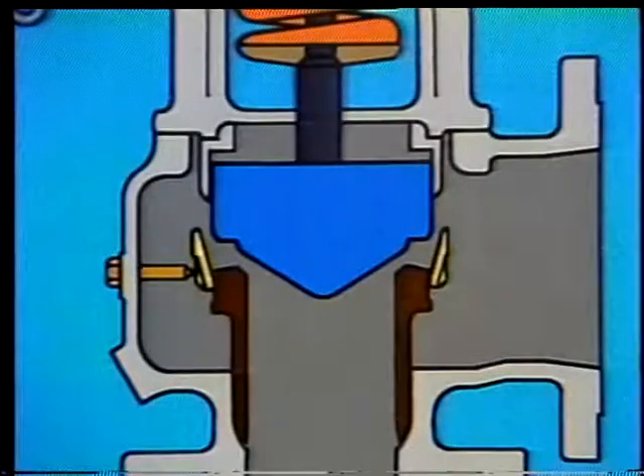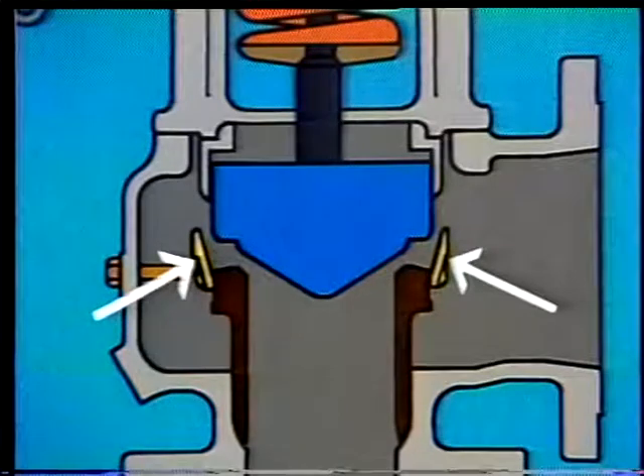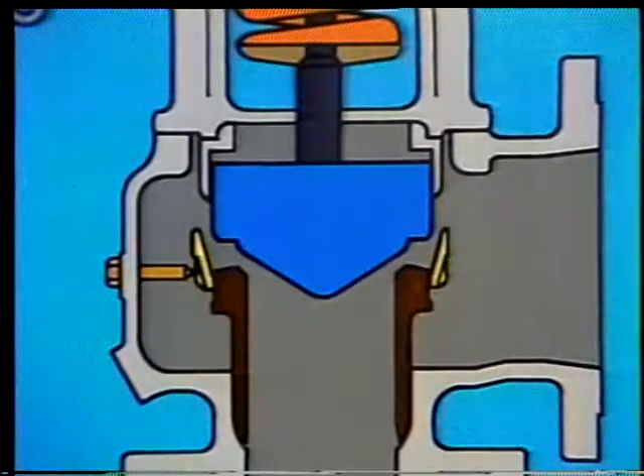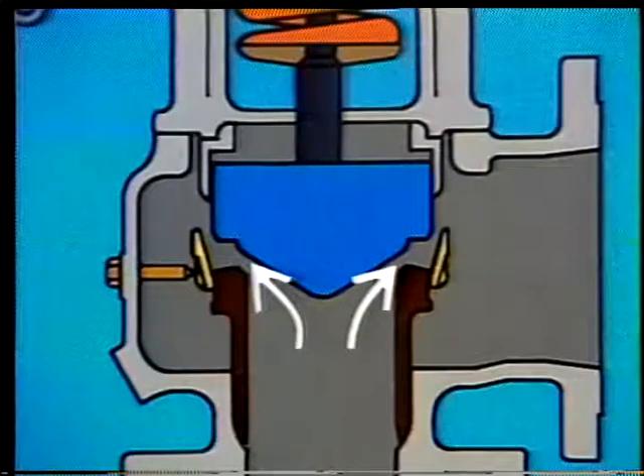Just as the popping pressure of a safety valve can be adjusted by turning the adjusting screw and increasing or decreasing spring tension, blowdown is adjusted by changing the setting of the adjusting ring. We can see how the position of the adjusting ring affects blowdown by studying what happens when the valve is closing. Remember that the position of the disc is determined by both the amount of system pressure and the velocity of the steam striking the disc.